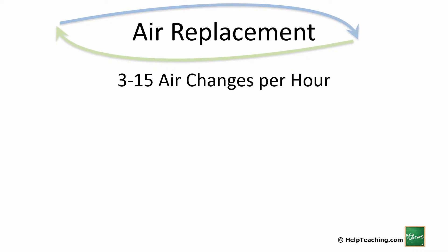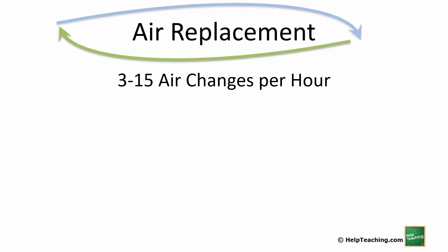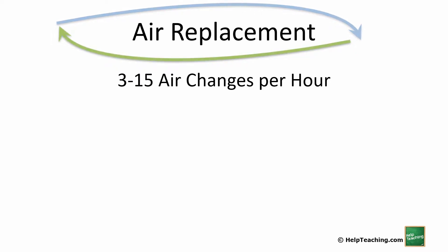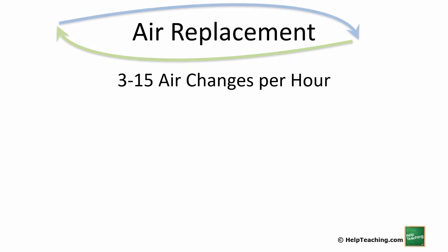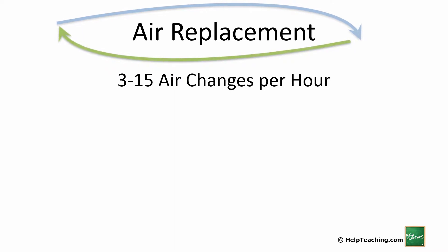For example, in a basement with 4 air changes per hour, whatever the volume of air in that basement is should be changed 4 times an hour — every 15 minutes that air should have been recycled through and you have fresh air back into that room. Some situations, especially a public space with smoking involved, may go up as high as 20 air changes per hour because they want to keep that air changing very quickly.